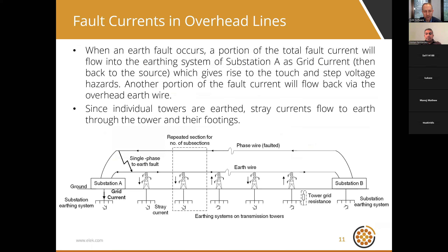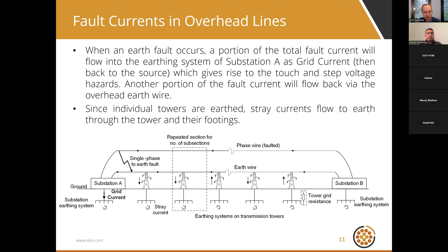Fault currents in overhead lines work a little differently and are more complicated. Looking at a schematic, multiple transmission towers are connected between substations A and B, each with their own earthing systems. Each tower also has its own earthing system. The towers carry phase conductors and there is one or more earth wires bonded at each tower and at each end of the line — that is, at the substations.